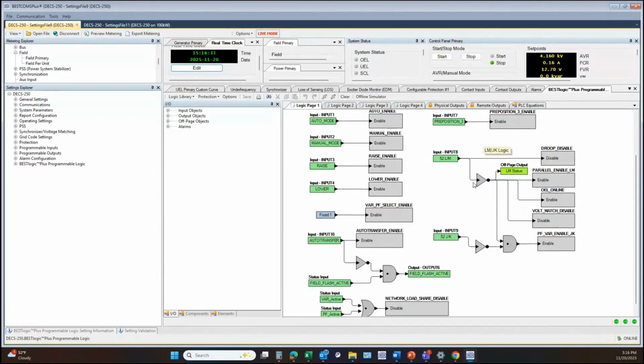So the NOT gate inverts whatever's coming into it. So if this is false, then the output's true. So we will enable the paralleling, we will enable our online OEL, and we will disable our voltage matching. And the combination of both of these inputs being false will end up causing the inputs to this AND gate to both be true. The AND gate requires all of its inputs to be true in order for its output to become true. So once both inputs are true, then we go into power factor or VAR control, whichever one we pre-select.